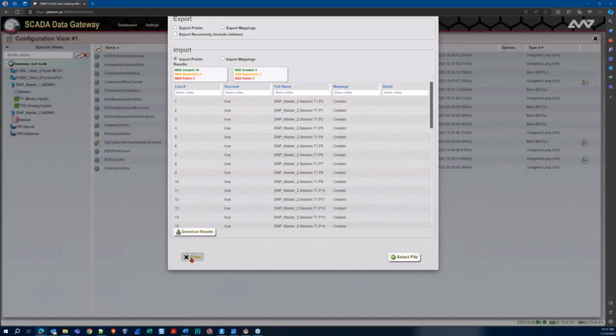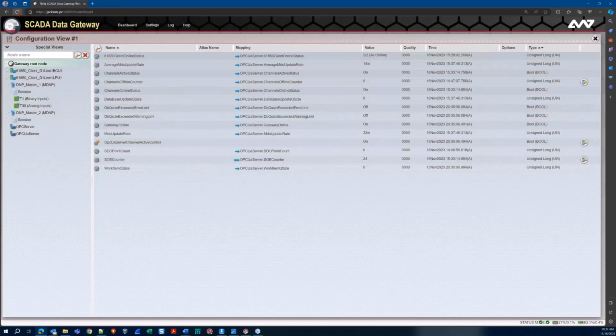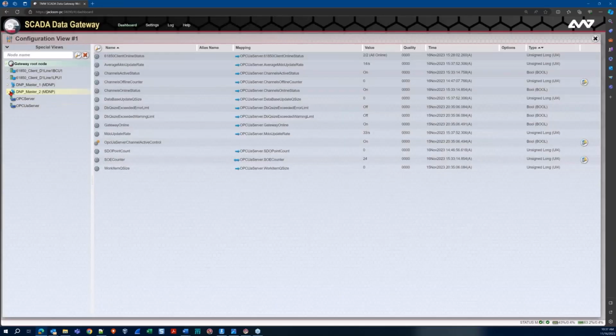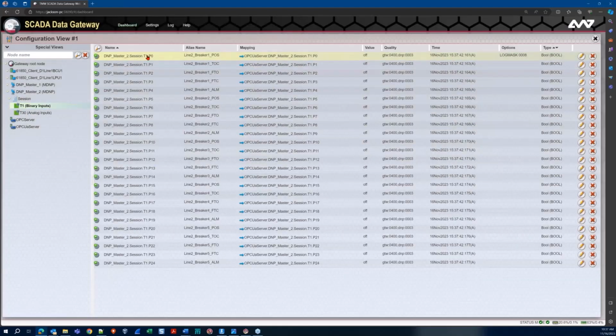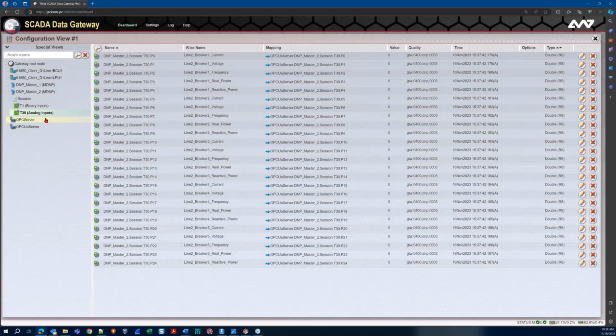So I can just close this out, give my gateway a refresh just to bring in the updated point types. And sure enough, session binary inputs, if I click on that, I can see that I've created those 25 points with the intelligent names that I took the time to apply for DNP Master 1, and now they've been applied down here to DNP Master 2.